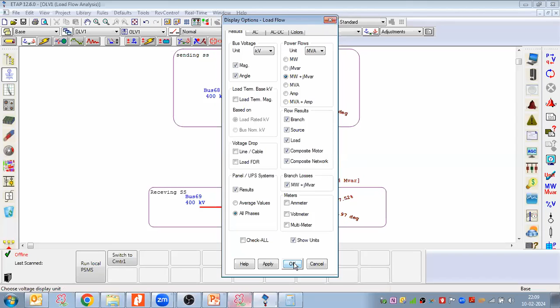So what result do we see here? From the sending substation, I have connected to a receiving substation, with no load connected to the receiving substation. Even so, 1.4 megawatts of power is shown flowing. At the same time, what does 1.4 megawatts plus 161.7 megavars mean? This is P plus Q, active power plus reactive power, and if you notice, the active power is 1.4 megawatts.